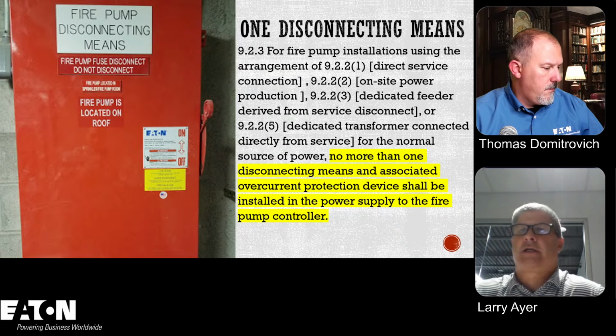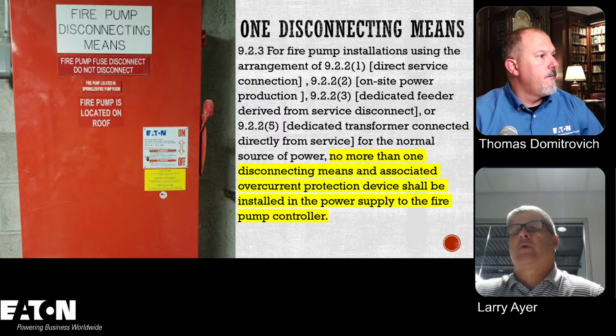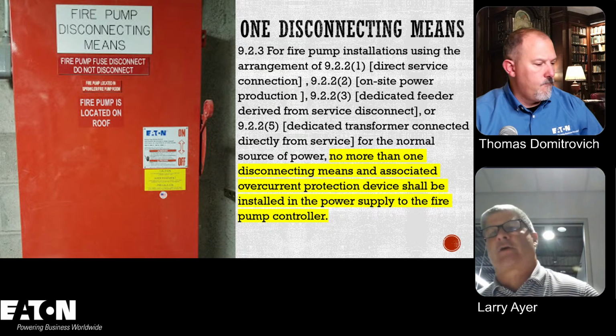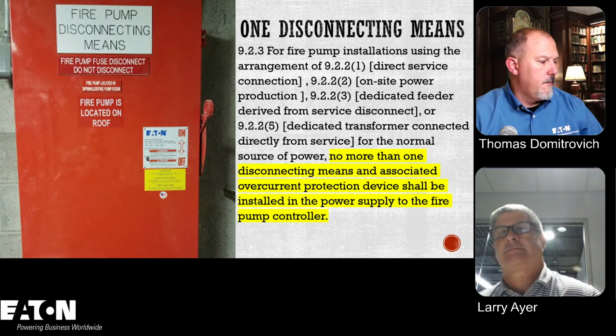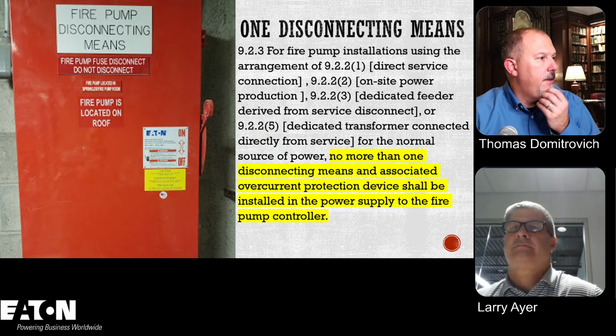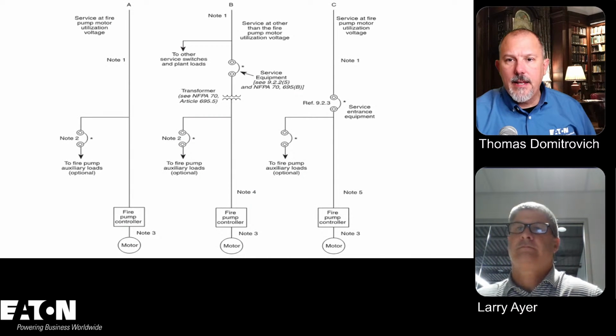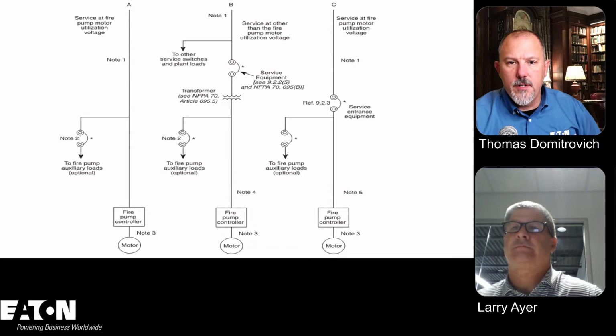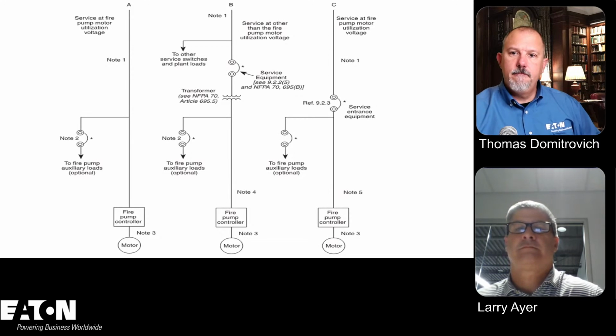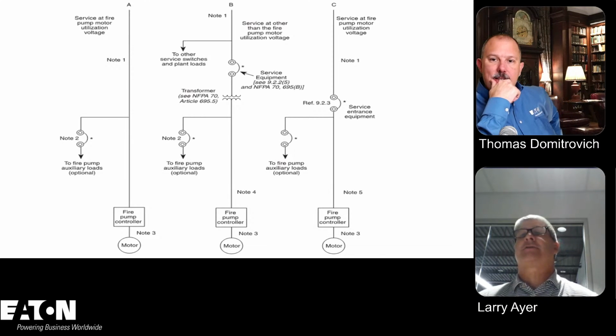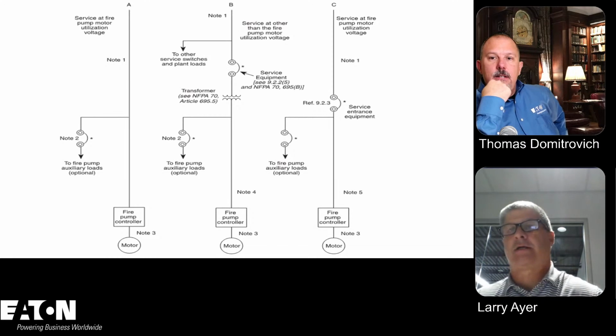This is similar to Article 695, but I highlighted the yellow part. No more than one disconnecting means and associated overcurrent protective device shall be installed in the power supply to the fire pump controller. Right. And I like this diagram. It sort of gives you a good overview, and that overview is taken from NFPA 20.